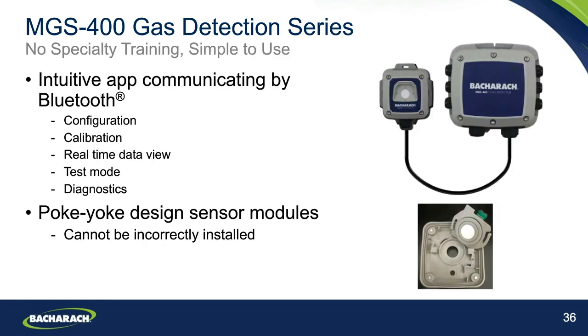No specialty training is needed for using the MGS-400. It is very simple to use. I mentioned the intuitive app communicating via Bluetooth, and that's used for configuration, calibration processes, and real-time data view on the system. There is an output test mode to provide functional tests of all of the detector's communication and output capabilities, and there are diagnostics in there which proactively help troubleshoot any issues that may arise. And the plug-and-play sensor modules that I mentioned have a poka-yoke design, which essentially means there is only one way to put those into the system. It is physically impossible to install them incorrectly, which again means there is no special training needed to perform that very quick, very simple sensor exchange. There is only one way to do it, so it cannot be done wrong.